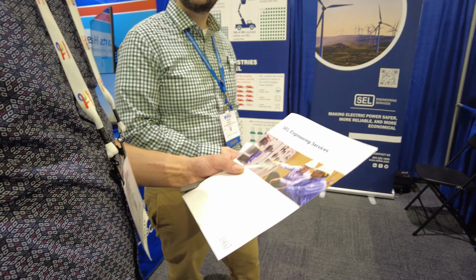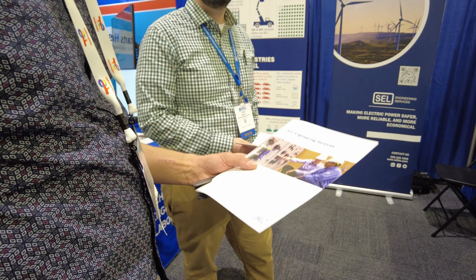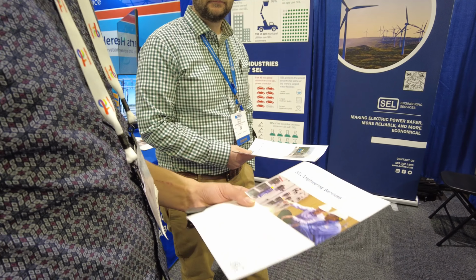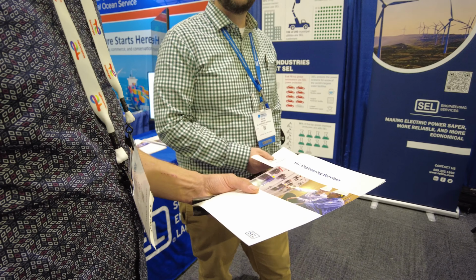In wind projects, we're not necessarily working with the actual wind turbine, but we're at the substation it's connected to, where the array cables come up underground or underwater. Wherever the breakers, transformers, bus work, and switchgear are, that's what we're actually protecting and controlling. On the communication side, we've got SCADA, automation, and integration, so operators onshore can send commands to the substation, operate equipment, and see all the data coming in, like voltages, currents, and power flow.